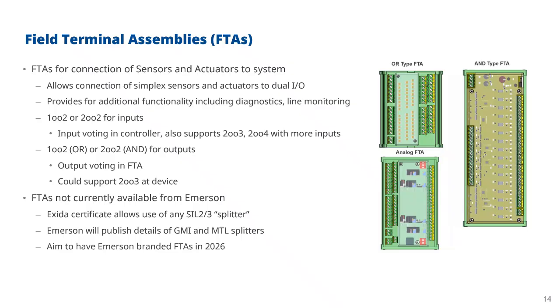There's another function that the field terminal assemblies can do as well, which is enhance the diagnostic level, including the possibility for line monitoring. So for example, on the input side, it's all very well to know that you've got 0 volts or 24 volts, but you might also want to know, are there other issues with the input? Is there a short circuit? Is there an open wire? Is there a cross connection to earth, or some other issue? And that's where these field terminal assemblies can give us additional diagnostics over and above what's available inside our standard I/O modules.